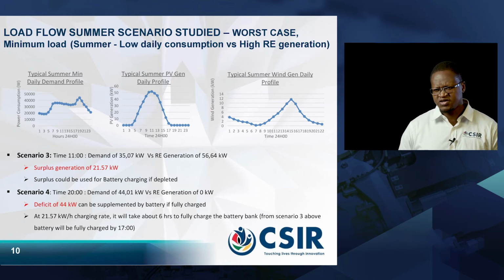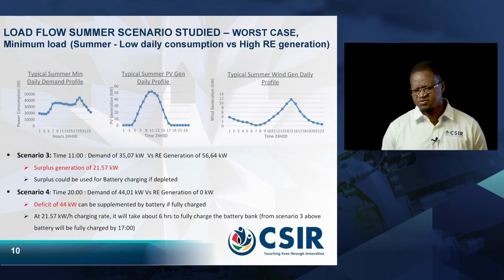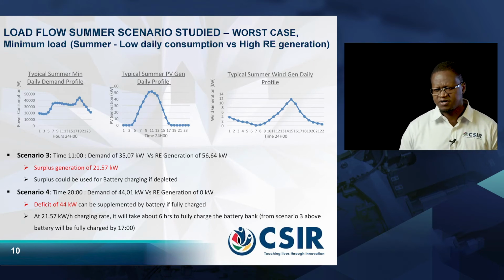The other extreme scenario or condition that we looked at was a summer minimum loading, where obviously you would be expecting stresses in terms of voltages, voltage rise. But in this particular case, I am doing generator adequacy, and that's what I'm looking at. So in terms of scenario 3 that we studied under this condition of summer minimum load, at around 11 o'clock, demand was around 35.07 kilowatts with a generation of about 56.6 kilowatts. That gave a surplus generation of 21.57 kilowatts.